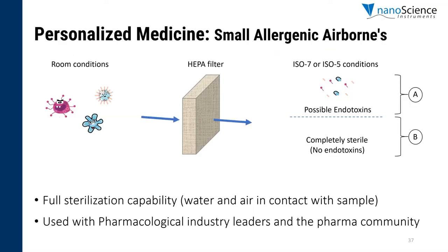The Fluidnatek technology can be implemented with HEPA filters, mainly to attain ISO 7 or ISO 5 conditions during sample development, meaning the sample development will be cleaner, with fewer particles depending on the classification you need. So depending on your needs, whether it's ISO 7 or ISO 5 conditions, we can make this happen.